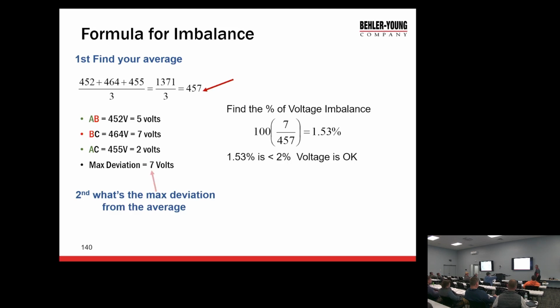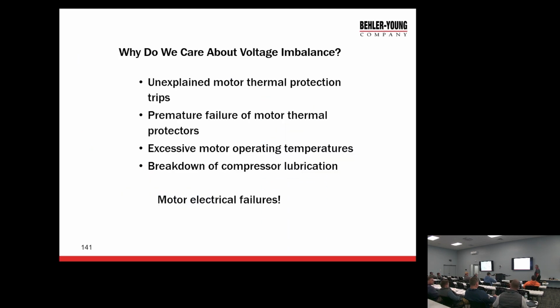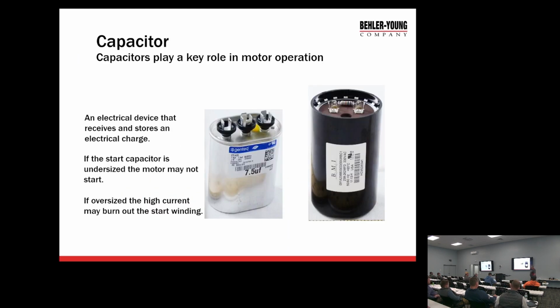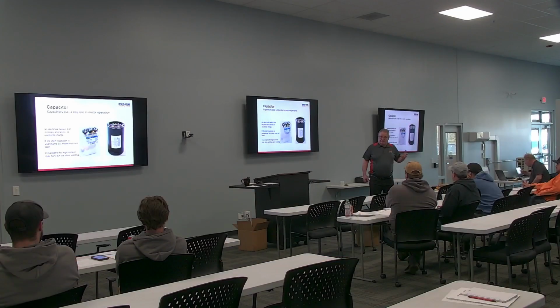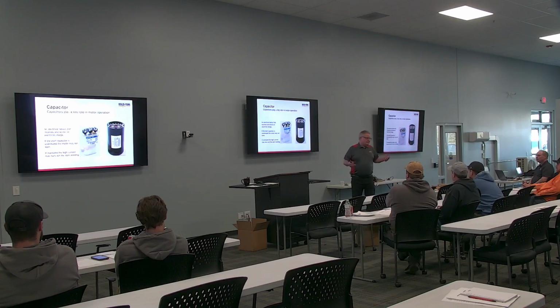So again, these tests here, especially if you're frying stuff like that, it's definitely worth something to check through. So capacitors, we want to look at these. We still use a lot of capacitors. We've bypassed a lot of them now because ECM motors don't use them. First of all, ECM motors are all 3-phase motors. ECM compressors, a compressor in a mini split is a 3-phase motor. 3-phase compressors are pretty easy to check. Check resistance. They should all be even. And then check the ground. You got anything at all to ground, they're dead.